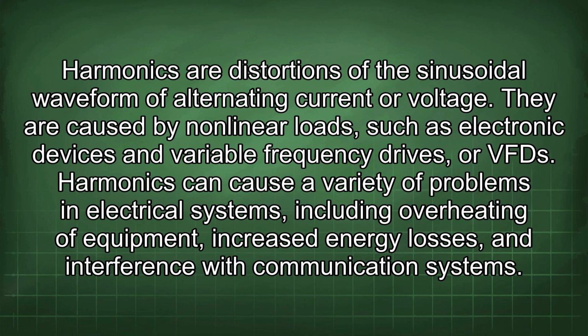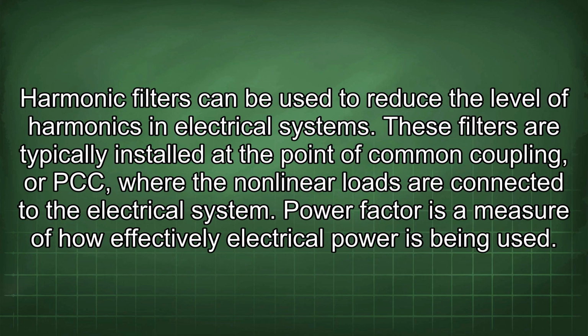Harmonics are distortions of the sinusoidal waveform of alternating current or voltage. They are caused by nonlinear loads such as electronic devices and variable frequency drives, or VFDs. Harmonics can cause a variety of problems in electrical systems, including overheating of equipment, increased energy losses, and interference with communication systems. Harmonic filters can be used to reduce the level of harmonics in electrical systems. These filters are typically installed at the point of common coupling, or PCC, where the nonlinear loads are connected to the electrical system.